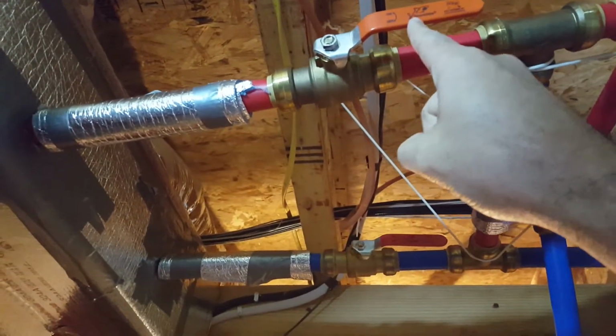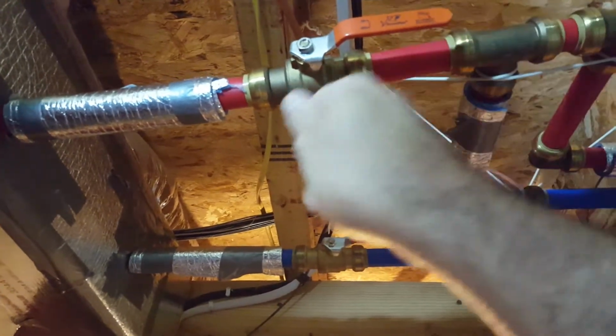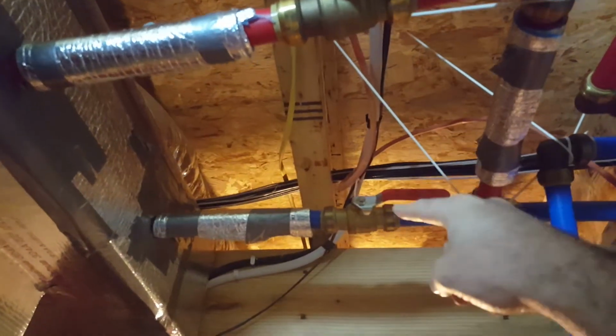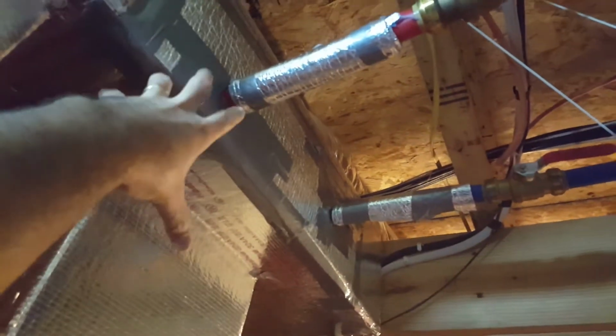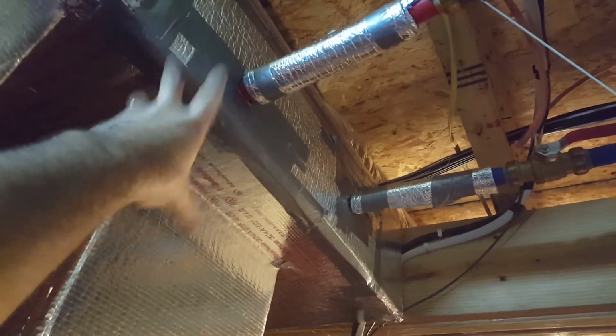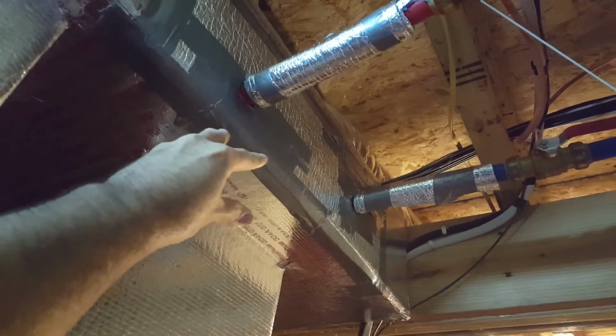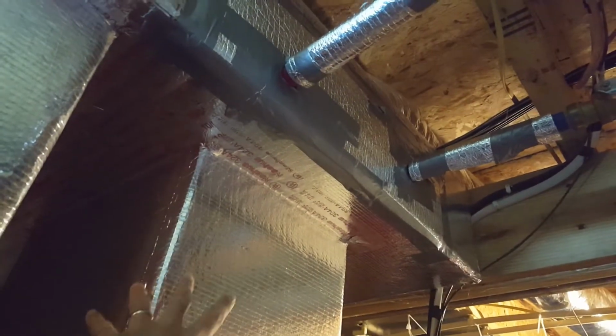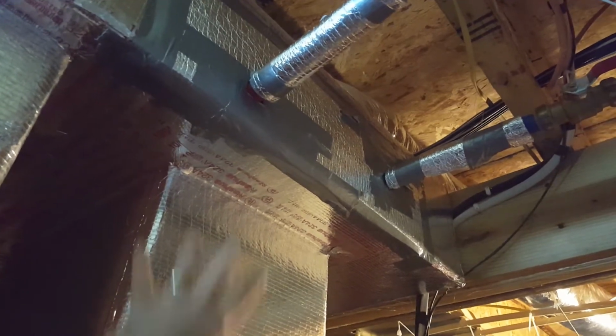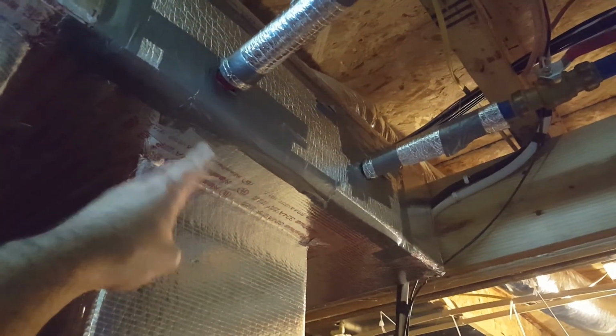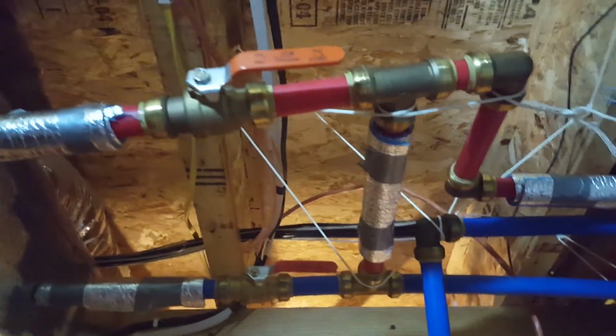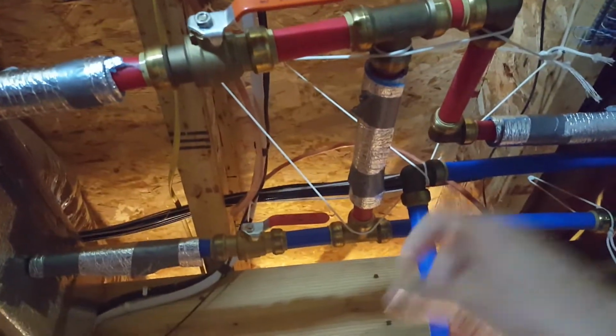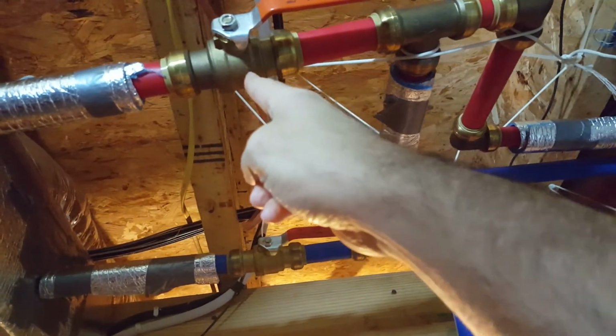Now back to this T, okay? If I close this lever down, so hot water can't flow there, and close that side too, that prevents hot water from entering the ductwork here in the summertime, because if you're running your AC, you don't want a bunch of hot air or 155 degree water in there. So we put in a manual bypass—we just close these levers, and the water can't get any farther than right there where you turn it off.